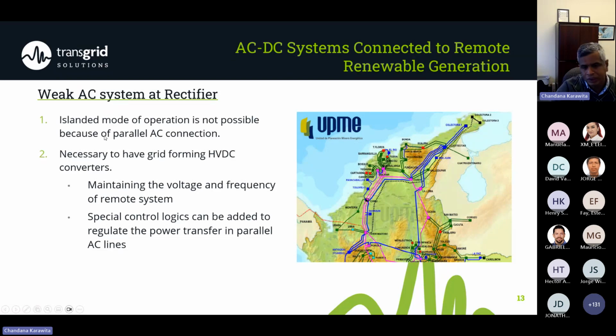One issue is the requirement for grid forming HVDC converters. The rectifier here should be in grid forming mode. Usually for offshore applications, when we have a single HVDC connected to offshore wind farms, we don't have to do grid forming. We can use islanded mode of operation. This means the voltage and frequency are kept constant.